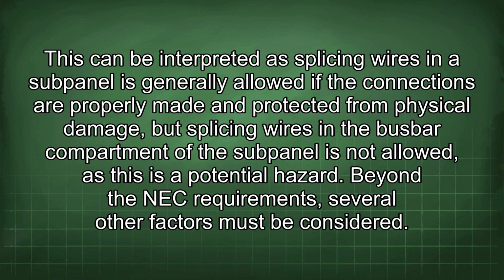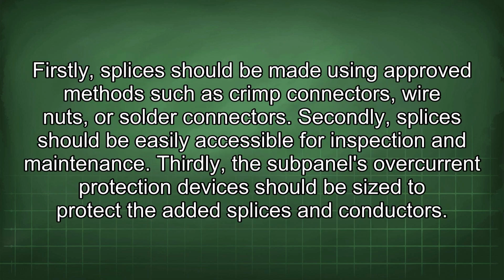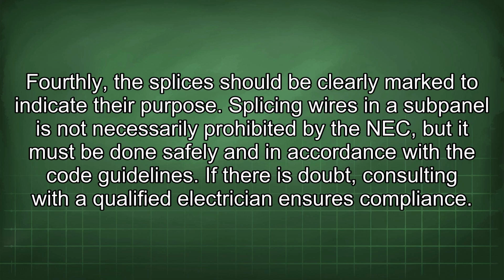and protected from physical damage, but splicing wires in the busbar compartment of the subpanel is not allowed, as this is a potential hazard. Beyond the NEC requirements, several other factors must be considered. Firstly, splices should be made using approved methods such as crimp connectors, wire nuts, or solder connectors. Secondly, splices should be easily accessible for inspection and maintenance. Thirdly, the subpanel's overcurrent protection devices should be sized to protect the added splices and conductors. Fourthly, the splices should be clearly marked to indicate their purpose.